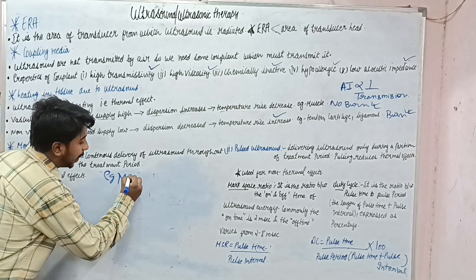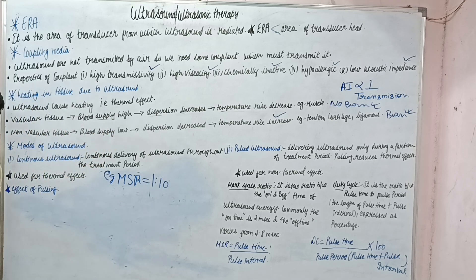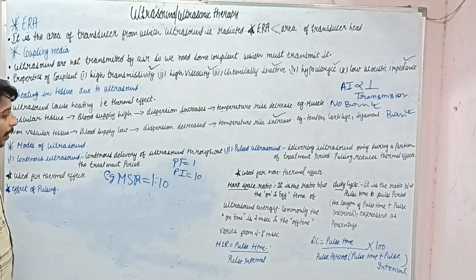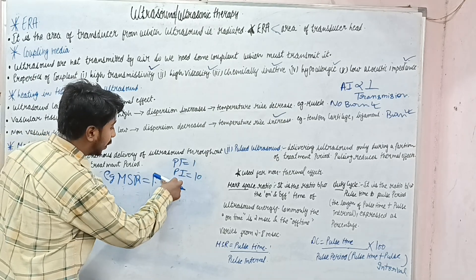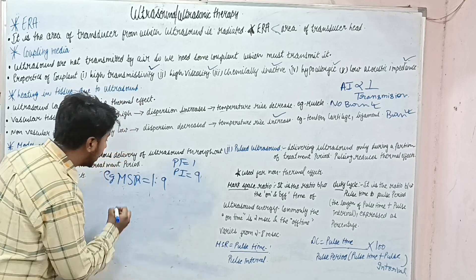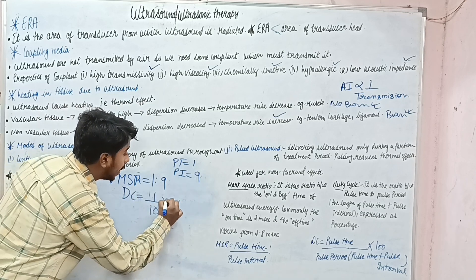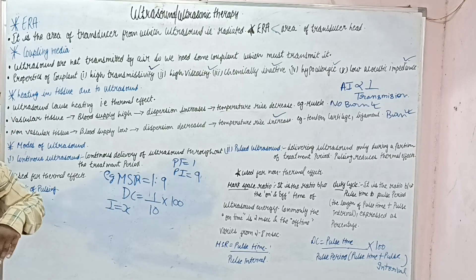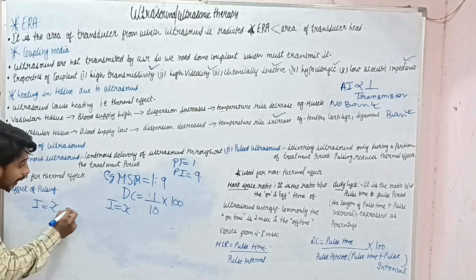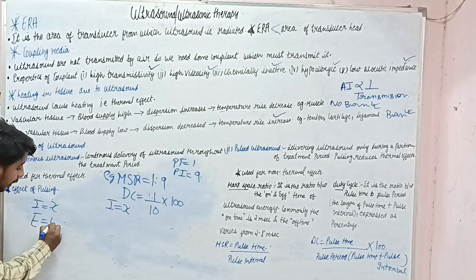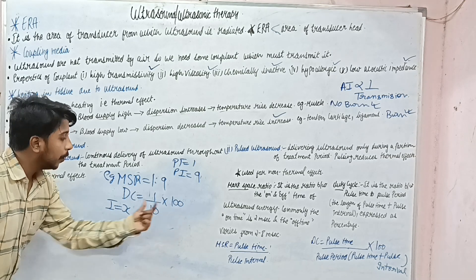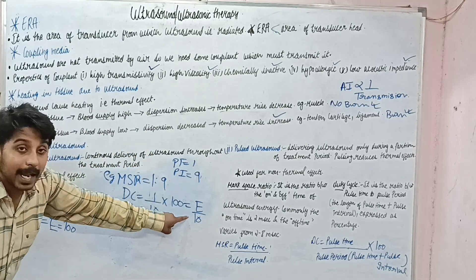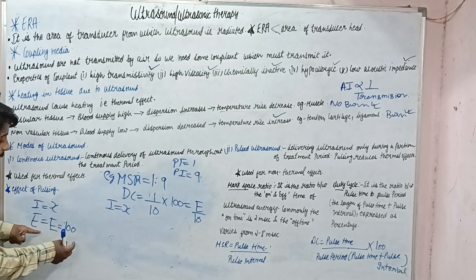Another example: mark space ratio is 1:9. Pulse time is 1, pulse interval is 9. Duty cycle = 1 / (1+9) × 100 = 10%. If intensity X is used in pulsed mode and the same intensity X is used in continuous mode delivering energy E (taken as 100), then pulsed mode delivers only E/10. So energy delivery is 10 times less compared to continuous mode at the same intensity.